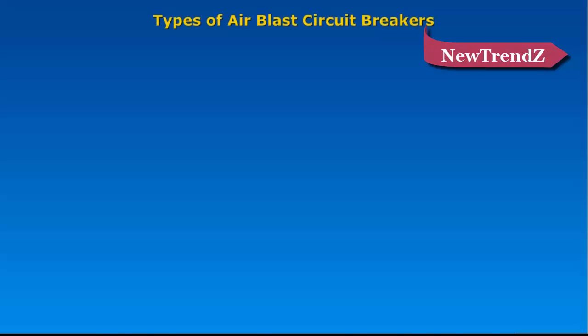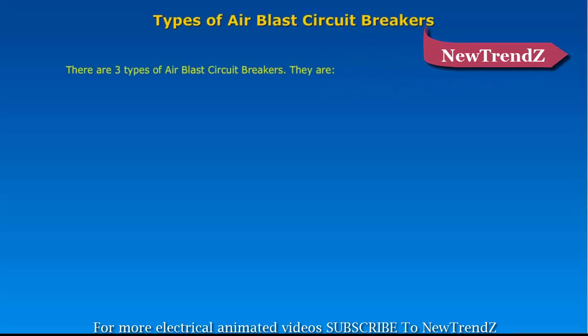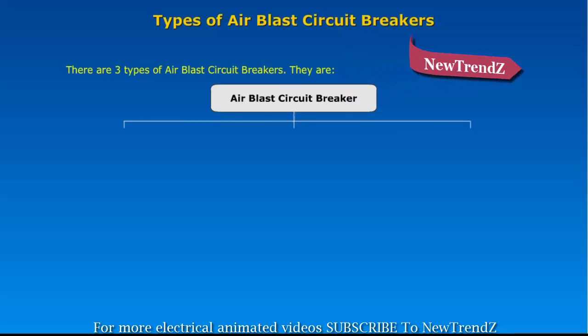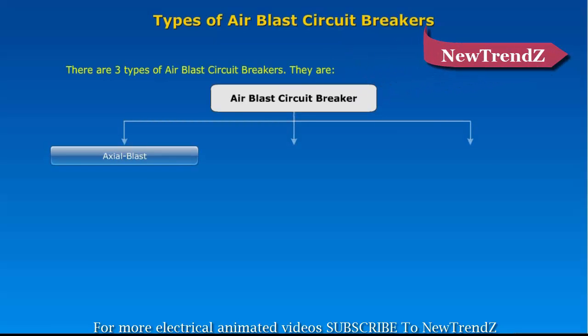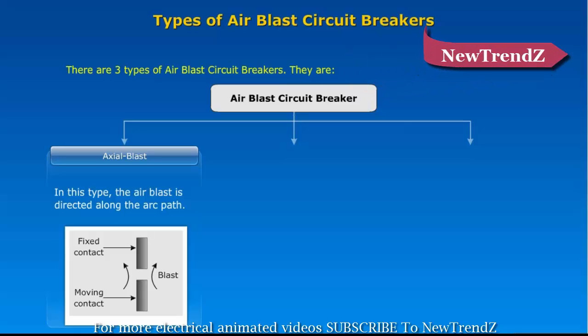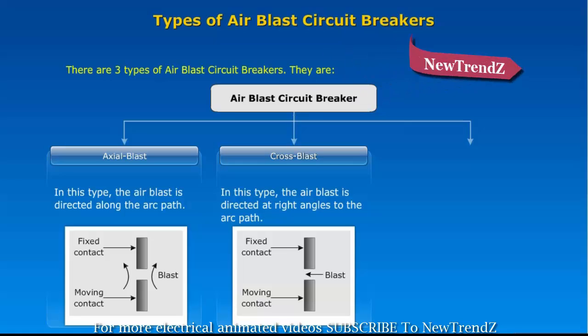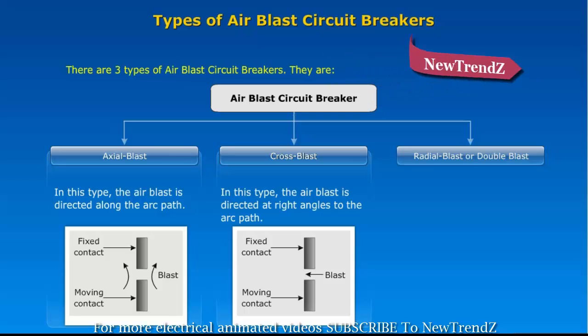There are three types of air blast circuit breakers: axial blast, in which the air blast is directed along the arc path; cross blast, in which the air blast is directed at right angles to the arc path; and radial blast, or double blast, in which the air blast is directed radially.